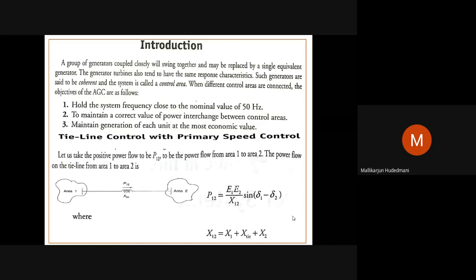In that control area, let us say a plant with a generator is situated. It is supposed to generate adequate megawatts and pump to the grid. When we say the word coherent, the generators are said to be in coherent operation if they are swinging with a single frequency. They are operating at the common frequency and their characteristics are very similar. Swinging with the common frequency, we call it coherent.